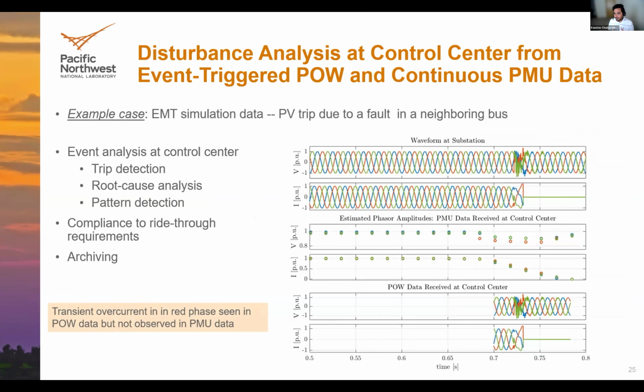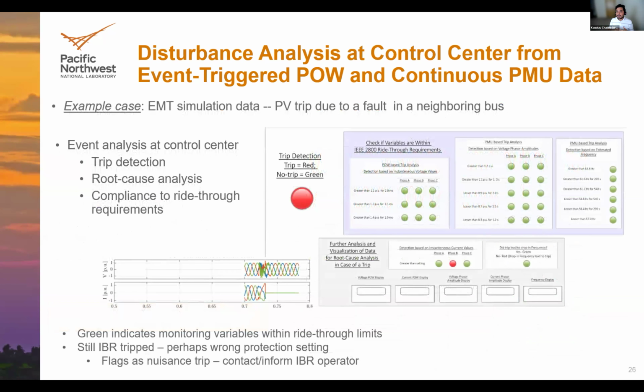So here I put an example. This is an EMT simulation of a PV trip due to a fault in one of its neighboring buses. What we see here is the voltage and the current waveform measurements. Again, the phasor data for this event is captured, as well as the event-triggered point-on-wave records using the method that I was mentioning. One interesting observation to make here is that there is a transient overcurrent in one of the phases, which is not captured in the phasor measurements. And this is what we will analyze more as we go on.